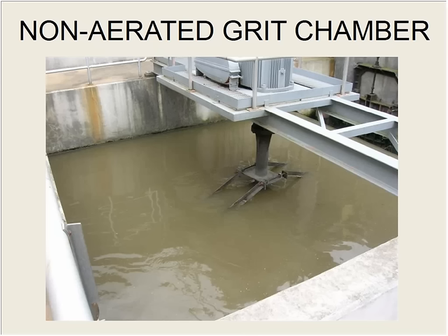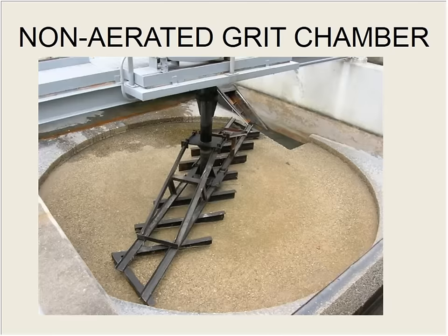This is a non-aerated grit chamber. Again, we've just expanded the area of flow, slowed things down so that grit can settle out in this chamber, and it's going to settle down into this area. And on a timer, this rake mechanism is slowly going to plow it down into that little sump you see up in the upper right corner there. And then they've got a screw conveyor to drag that material out of there.